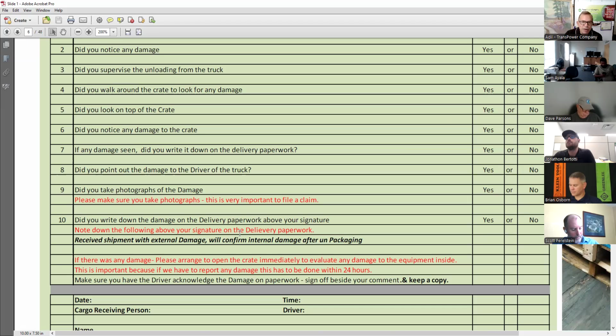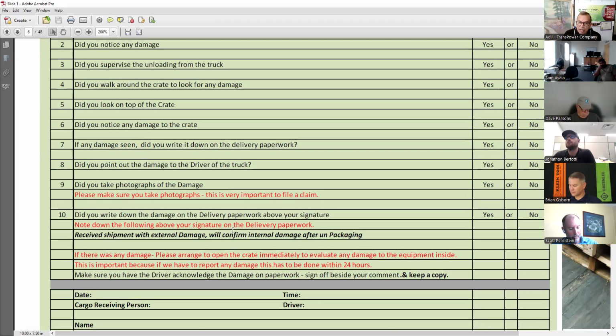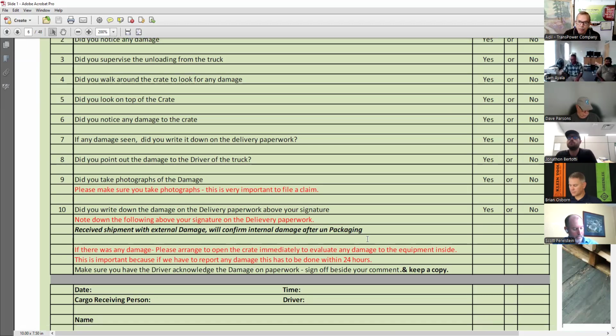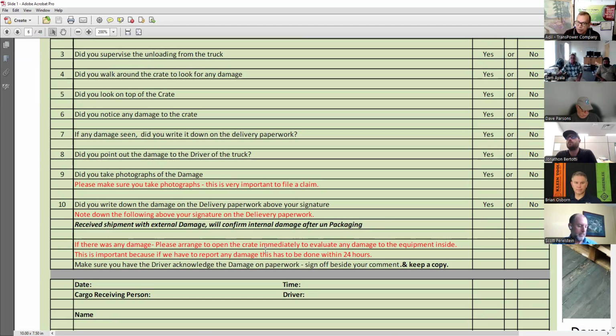Write down on the delivery paperwork from your UPS, FedEx, or freight carrier — because when you sign that delivery note, there's fine print saying received shipment in good condition. So write received shipment with external damage, will confirm internal damage after unpackaging, because most times equipment is received by the receiving department and may not be opened immediately. If there's any damage, arrange to open the crate immediately to evaluate damage to the equipment inside. This is important because any damage must be reported within 24 hours.